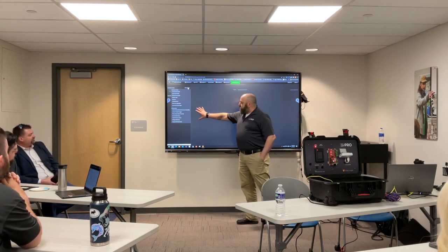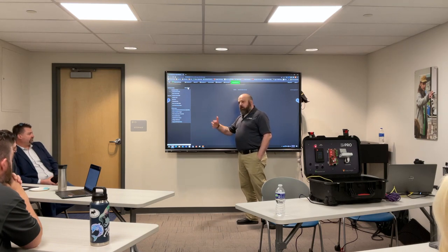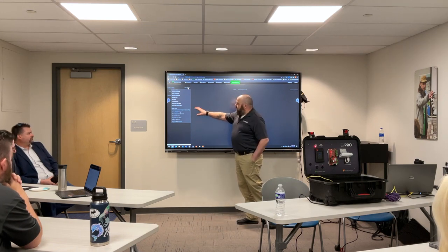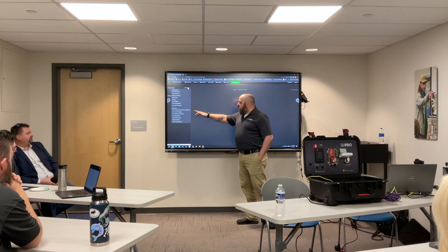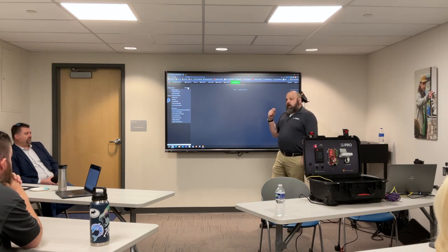And then at the bottom we have server-based rules. These are ones that are going to be controlled by the server. So if the server goes offline, these rules won't work. But you can see things like three-swipe override is oddly a popular one. You can present your badge three times to any reader or any specified reader and affect other downstream readers.